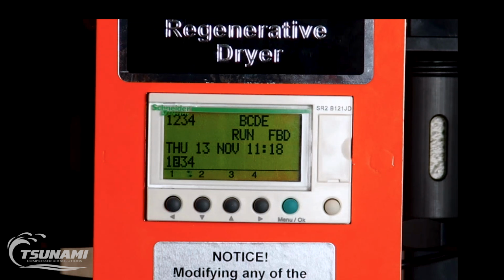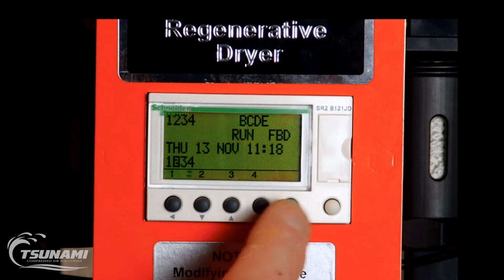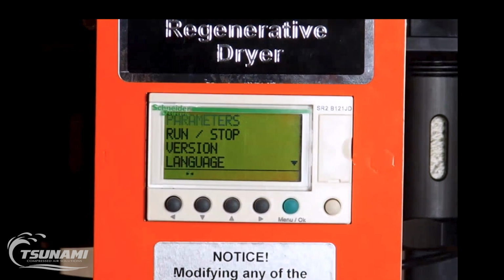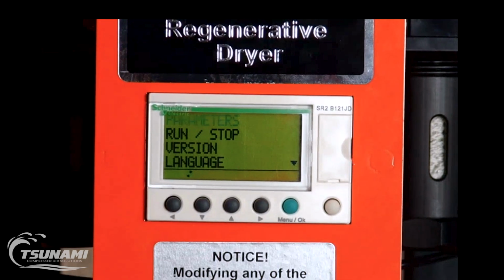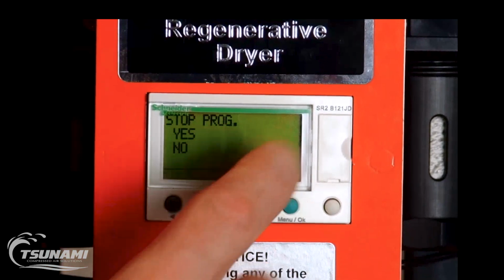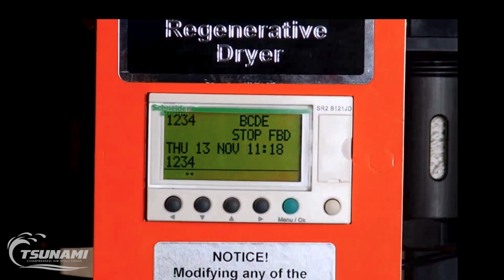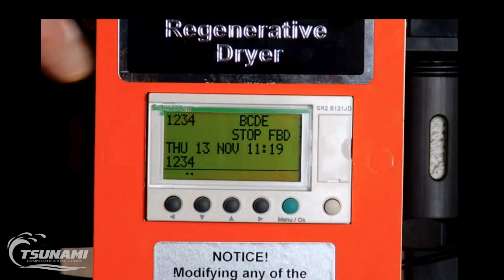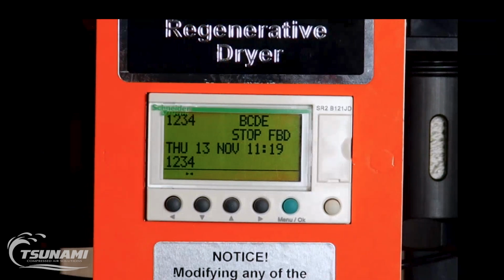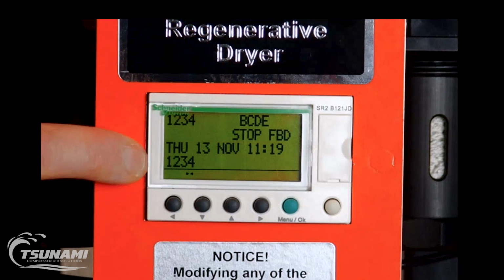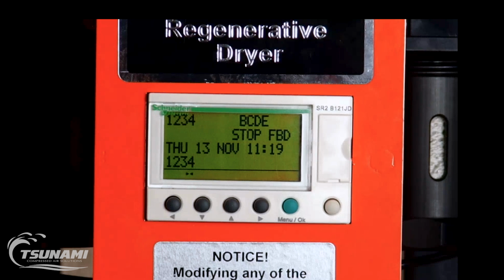One of the things that we want to talk about is accessing the parameters. More often than not, we're going to tell you to hit the menu button, go down to run stop until it's flashing, hit the menu OK button, stop the program, and we want to answer yes. So now you can see we've got stop on the PLC, as well as none of the outputs are highlighted underneath that date code. And as you can see, the 2 dots down below are now no longer spinning.